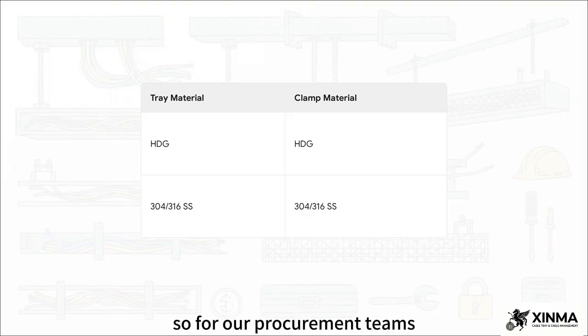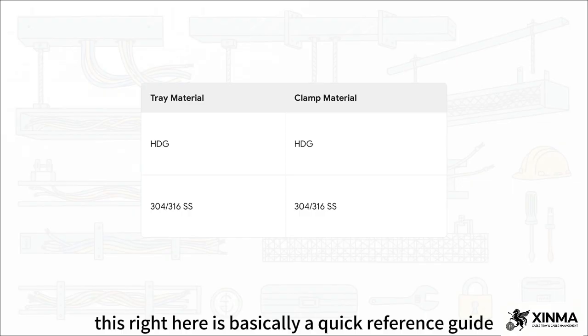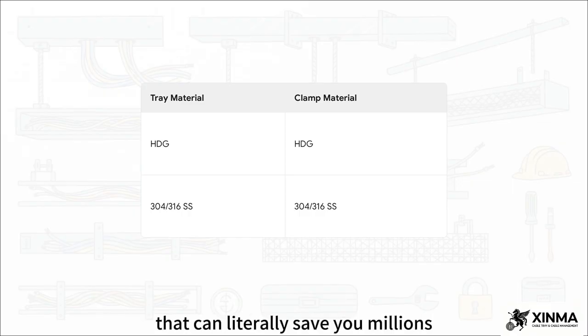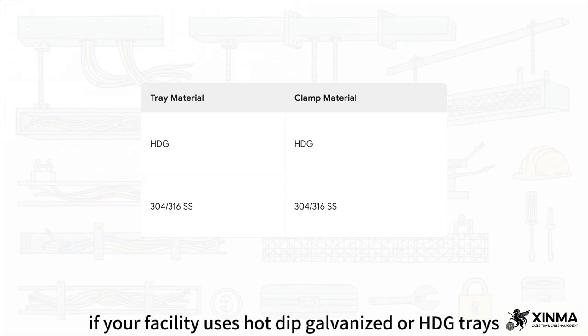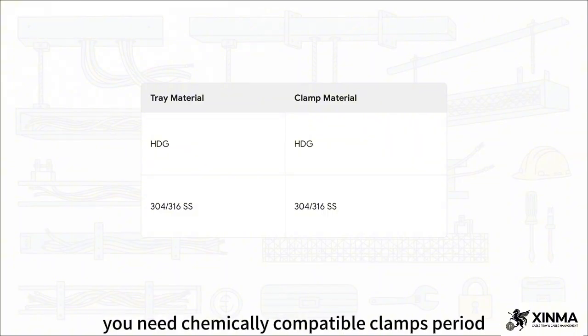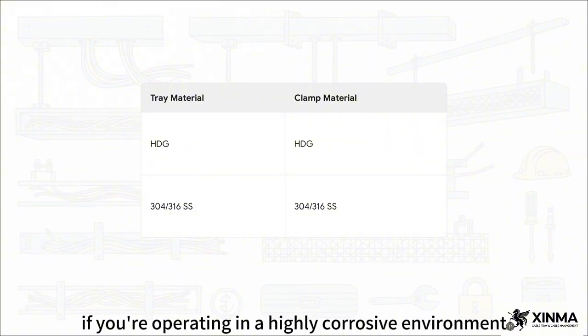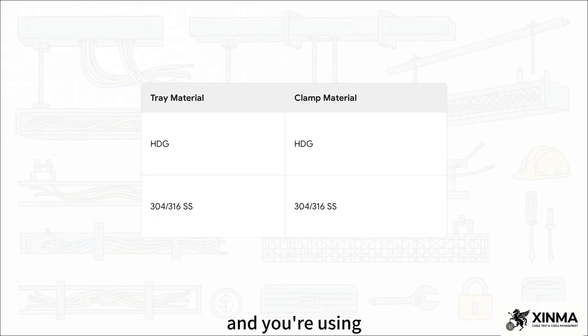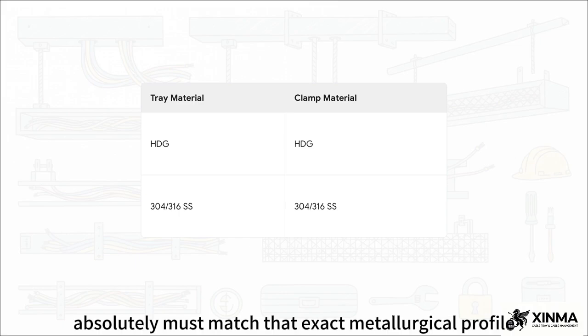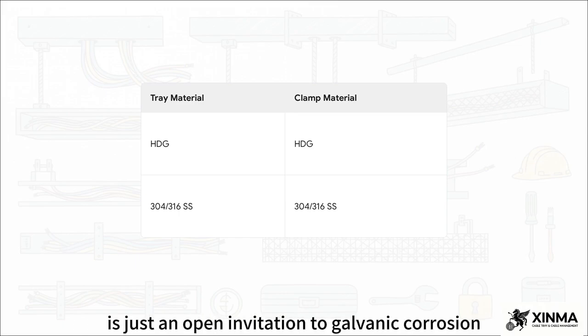So for our procurement teams, this is basically a quick reference guide that can literally save you millions in replacement costs. You absolutely must specify the exact right material for your clamps. If your facility uses hot-dip galvanized or HDG trays, you need chemically compatible clamps, period. If you're operating in a highly corrosive environment using 304 or 316 stainless steel trays, your clamps must match that exact metallurgical profile. Mixing the wrong metals is just an open invitation to galvanic corrosion.